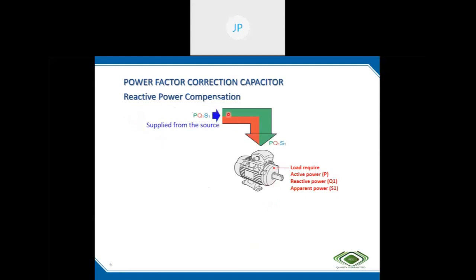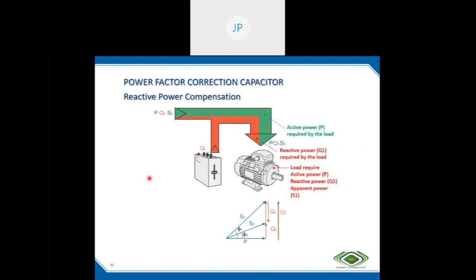You can see the green is active power, red is reactive power, and the total power is almost double the reactive power, so the power factor is very low. We can improve this power factor by connecting a capacitor, and the capacitor delivers some reactive power. It is almost equal to the requirement, and only the balance needs to be drawn from the source. So the net or apparent power drawn is reduced, but the active power remains the same. The power factor is improved.